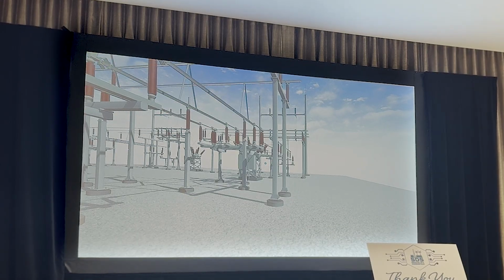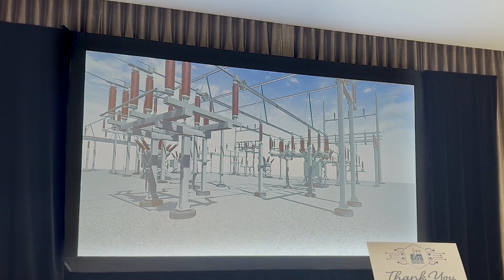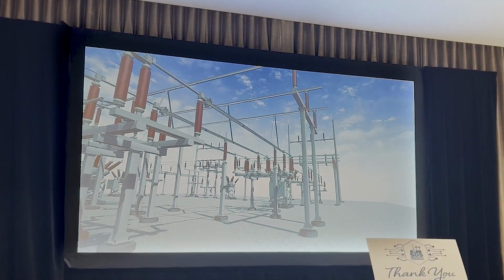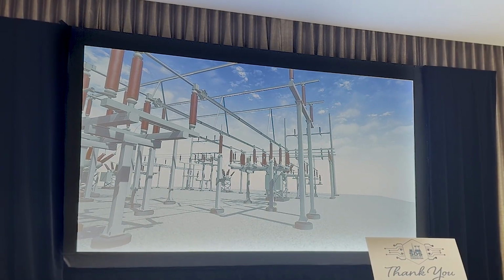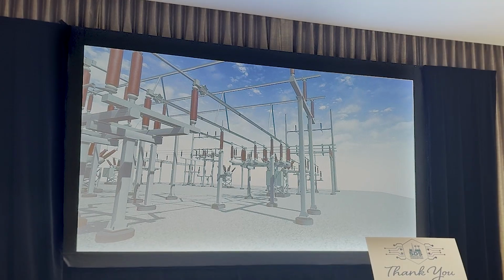This is also enhanced, so a new version of this actually just came out today. It got uploaded to the website today. That version lets you do things like sweeping clearances down the bus. What it'll do is take a value that's actually in Primtech in the model manager for my phase to ground, and sweep that down the bus all the way across the station.